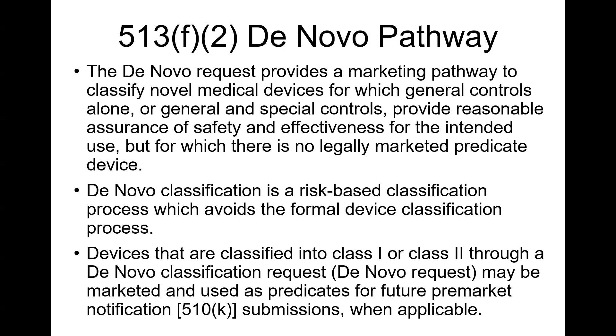I'm pausing here and noting we're moving on to class 3 products, even though technically de novo isn't considered a class 3 product. We're going to group it the same just for purposes of this intro lecture because it oftentimes requires clinical data. And as a note, what you're doing is you're in effect creating a new medical device category because it doesn't exist. So you go through this decision flow whereby if you've determined you're legally regulated as a medical device and you've determined you're not eligible for any class 1 or class 2 devices, by default, you're either going to have to submit a PMA or you're going to have to create this new category, and you do so through this de novo process.